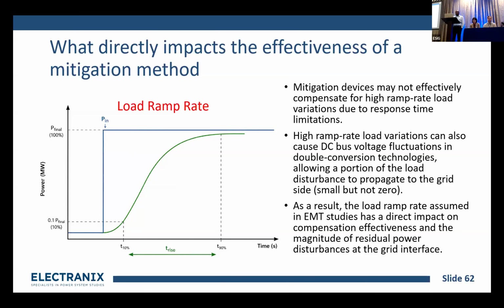So the important ones is, that's the place where your real-code UPS models come into the picture. You can change your load at the DC level or the GPU level as a step, but it'll show up at the medium voltage level as a ramp or some kind of function. In certain cases, if you look at single-phase power supply units and use a real-code model, you might see your load change 100 megawatt, but the high side of the power supply might change 120 megawatt. You have overshoot there. So essentially, you need to mitigate more than the load change in certain cases. Those things need to be captured properly. That's where the real-code model's importance comes from.